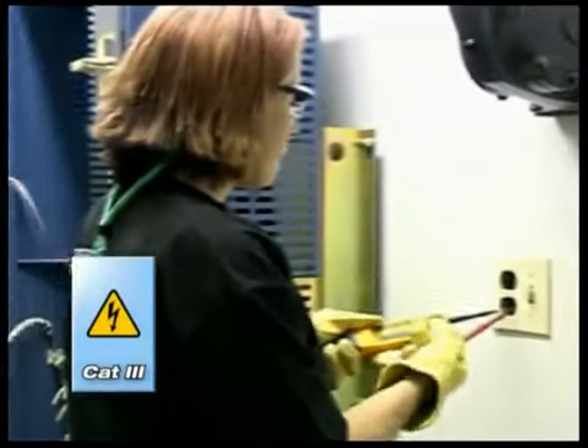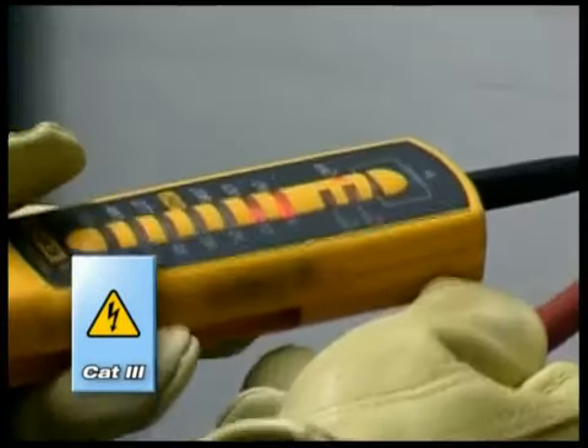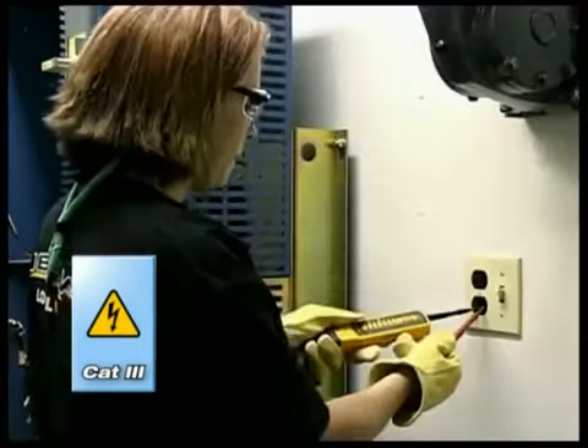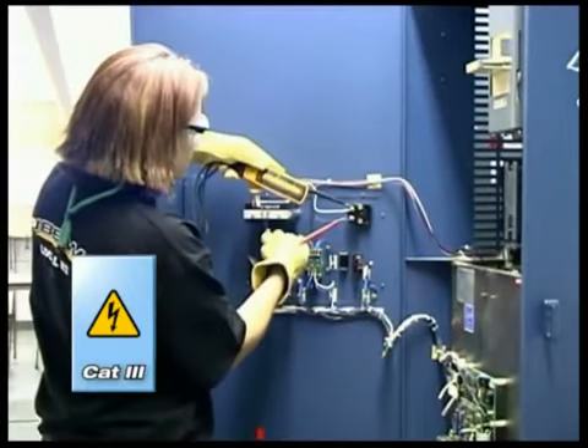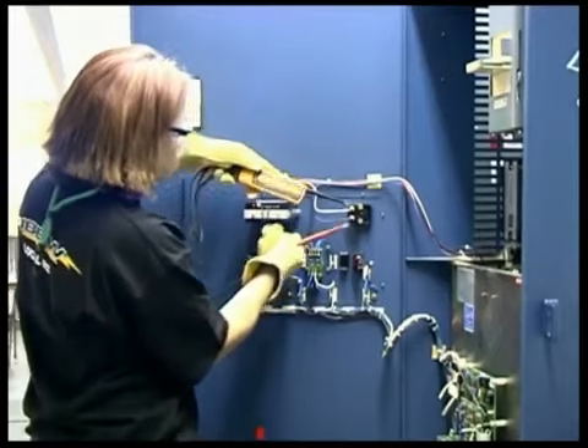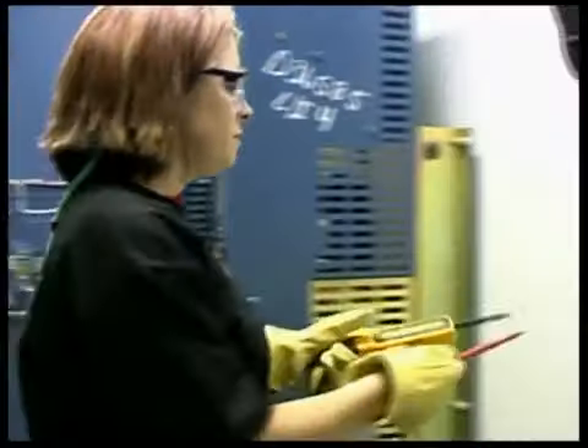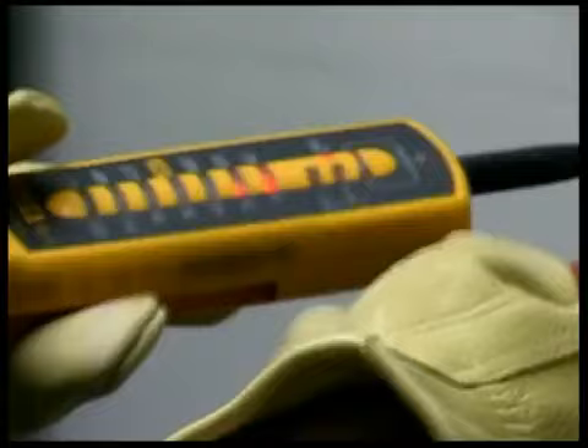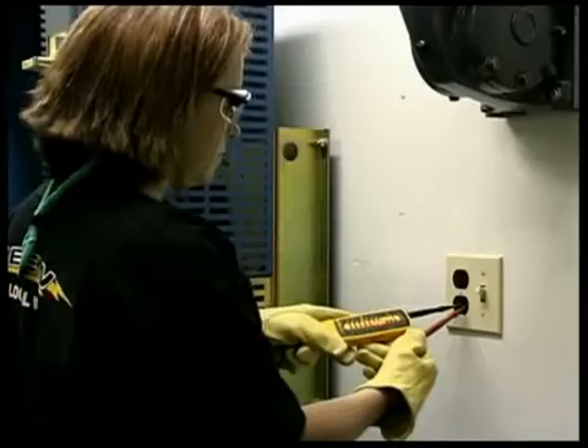Use the three-step test method. First, test a circuit you know is live. Next, measure the target circuit. But before you conclude that circuit 2 is dead, retest the known live circuit. This way, you know your meter is working.